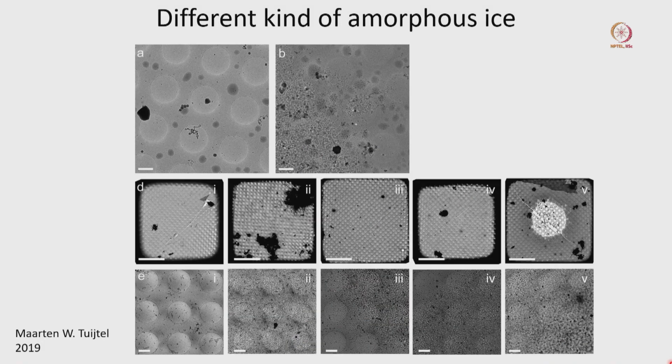If the sizes are very large, something like bacteria or viruses, generally we go to the smaller magnification, so generally 4000, 6000, 10,000. Generally for tomography, cryo-electron tomography, we use low magnification, because most of the time we are collecting data for large molecules like bacteria, viruses, cells. But for protein samples, DNA-protein or lipid-protein, we have to go to high magnification.